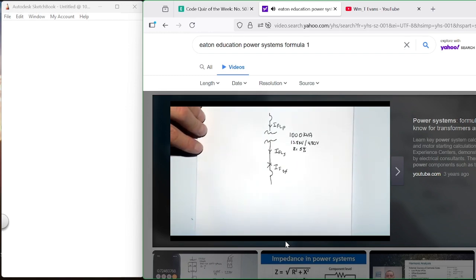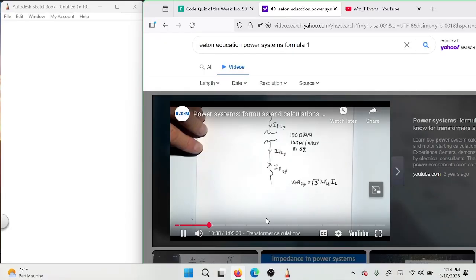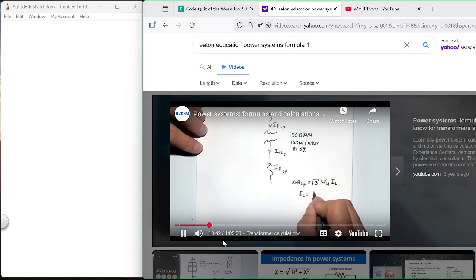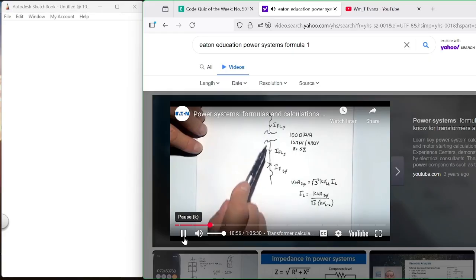So we're going to go back to the equation that we started with, and we talked about for three-phase power, which is kVA three-phase equals square root of 3 times kV line to line times I line. So if we solve for the current, I line equals kVA three-phase divided by square root of 3 divided by kV line to line. Then we just substitute in if we're on the primary or the secondary to calculate our current. So for example, current I full load on the primary is 1000 kVA divided by the square root of 3 divided by 13.8 kV.